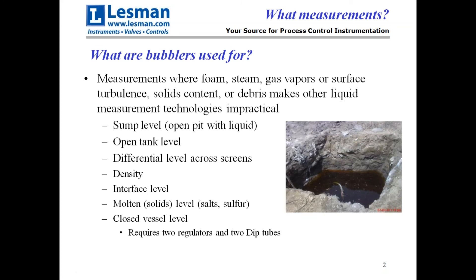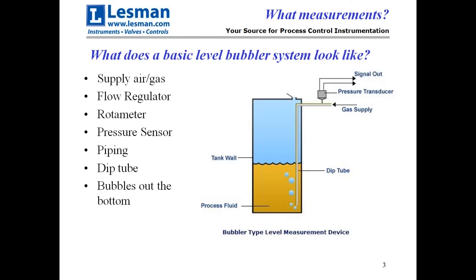For those of you who might not have been involved in this for very long, let's go over what bubblers are basically used for. A bubbler takes a measurement where other things interfere with other technologies — like foam, steam, water that condenses on the horn of a radar antenna or on the diaphragm of an ultrasonic transducer, when you've got a lot of surface turbulence that can't be averaged out, or where there's solid content or debris that makes other measurement technologies impractical.